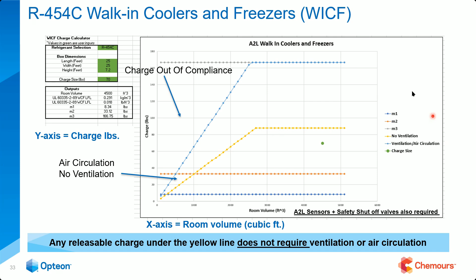Now, up here under the blue line, the top right, you would need air circulation and ventilation. Think about it here. We've got lots of pounds in the charge. The charge is quite high. We have a lot of room up here, but the charge is such that we're going to need air circulation and ventilation. Pardon me. Okay, and the perfect place, the sweet spot where we want to be, is right here. Anything below this yellow area, where we don't have that much charge and we've got quite a bit of cubic feet, the only thing you would need there is room volume.